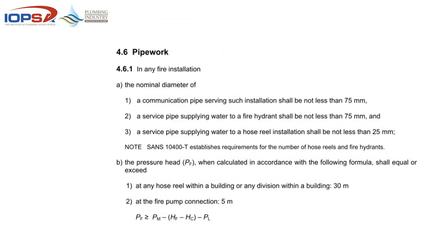For pipework in any fire installation, the nominal diameter of a communication pipe serving that installation shall not be less than 75mm. The service pipe supplying water to a hydrant shall not be less than 75mm, and the service pipe supplying water to a hose reel installation shall not be less than 25mm. Referring back to SANS 10252 Part 1, the 75mm is a given — any communication pipe shall not be less than 75mm, and if it exceeds 50 meters it shall be upsized to 110mm. If it's more, a ring main must be installed.